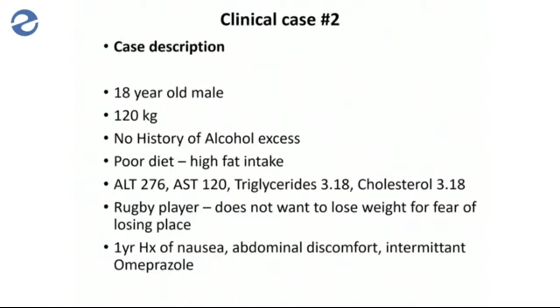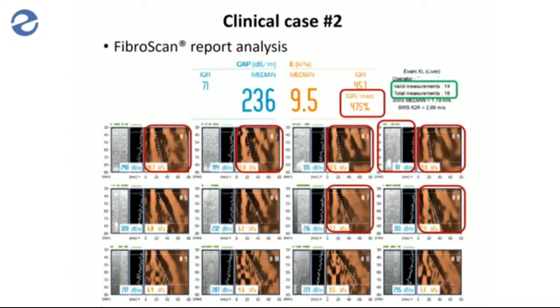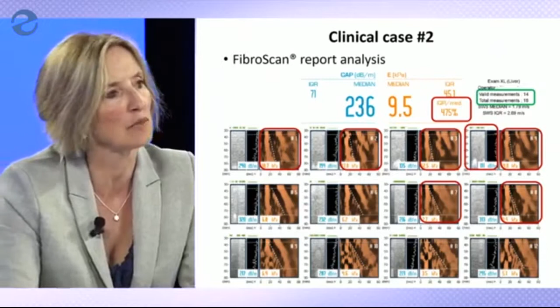So let's have a look at his scan. FibroScan was 9.5, CAP score of 236. But we can see by the scan you've got an IQR percentage there of 475, so it's not a valid scan. It wouldn't be put on the patient's records for fear of somebody misreading that scan, but we've got valid readings, which are excellent. And there's the odd valid reading in there, but go to the next slide.